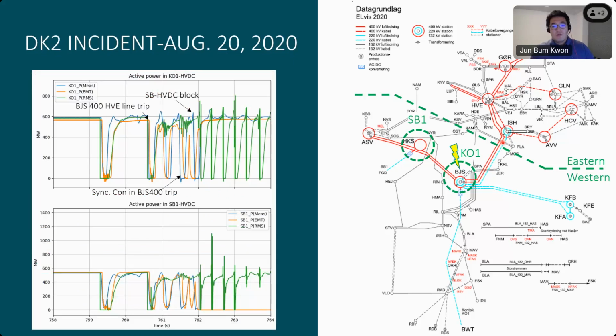We made comparisons involving measurements from the stations and recreated the same cases using system-level EMT simulations as well as the RMS environment we have. You can see clear differences: RMS was able to show some commutation failure, but the starting point of the oscillations, the oscillation frequencies, and sequential events caused by multiple devices were not captured well in RMS. The EMT environment, however, easily captured these events by applying the same type of fault observed in real life.